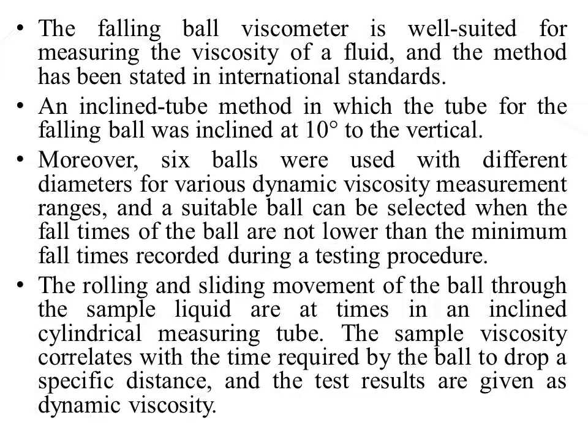The rolling and sliding movement of the ball through the sample liquid takes place in an inclined cylindrical measuring tube. The sample viscosity correlates with the time required by the ball to drop a specific distance, and the test results are given as dynamic viscosity.